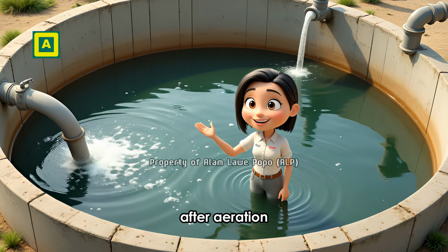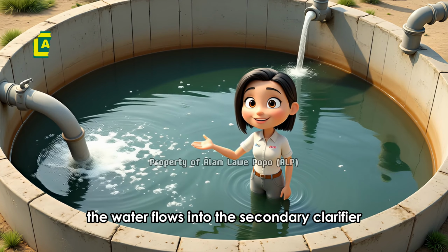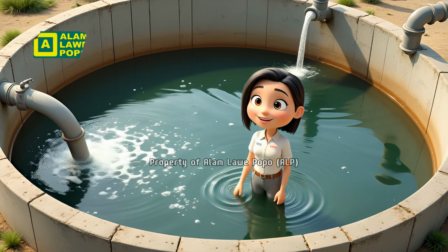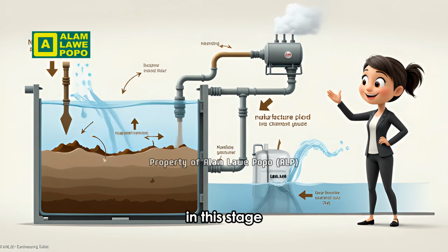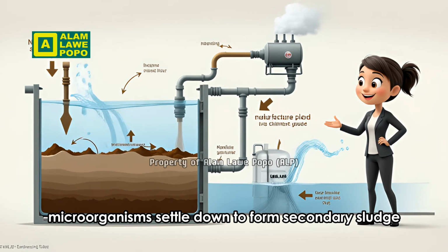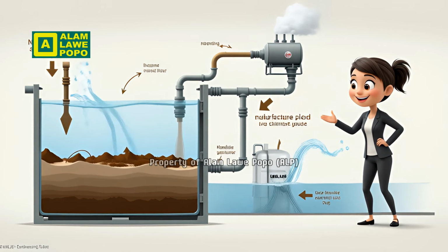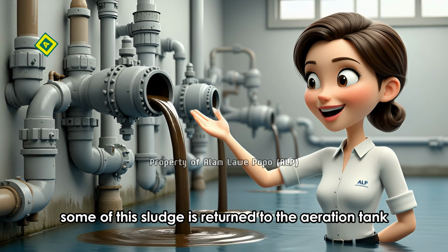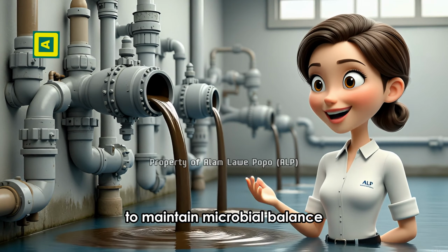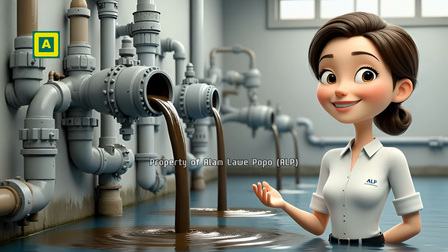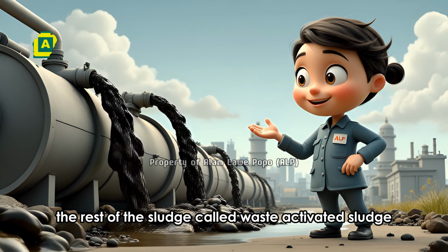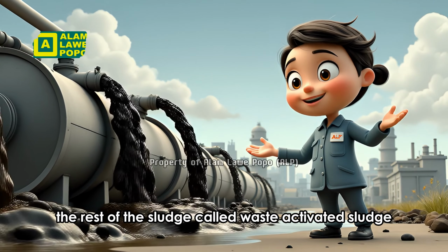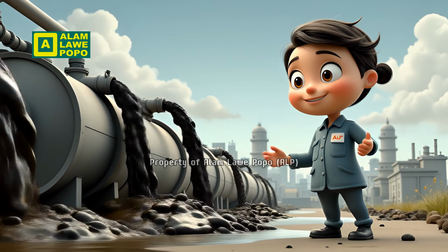After aeration, the water flows into the secondary clarifier. In this stage, microorganisms settle down to form secondary sludge. Some of this sludge is returned to the aeration tank to maintain microbial balance. The rest of the sludge, called waste-activated sludge, is sent for further treatment.